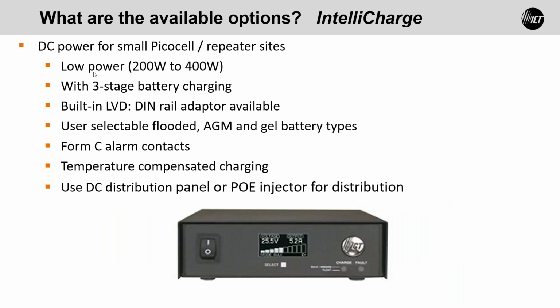For smaller sites - pico sites, repeater sites, or maybe a pole mounted enclosure with DIN rail products - we have our IntelliCharge, which is a great product. If your requirements are 400 watts or less, it has 3-stage battery charging, built-in low voltage disconnect, DIN rail adapter, and a user selector for flooded, AGM, or gel type batteries. It's also got Form C alarm contacts.